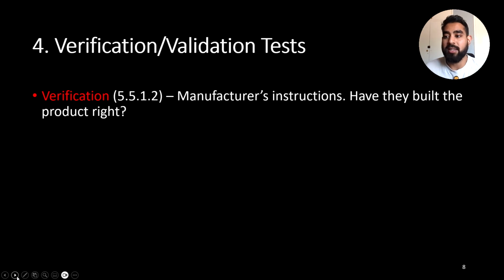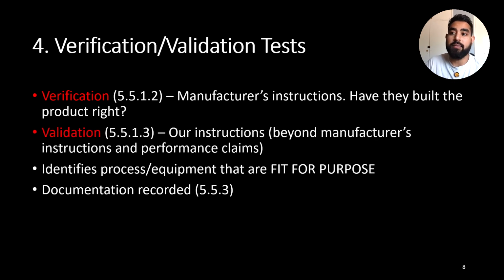We would then need to verify or validate the new piece of equipment. And so what do these mean? Verification is the testing of the equipment to the manufacturer's standards and parameters to see if they have built their product right. Validation aims to test the kit outside of the manufacturer's claims, according to our own protocols. And this is to see if it is fit for purpose. Again, this is all documented.